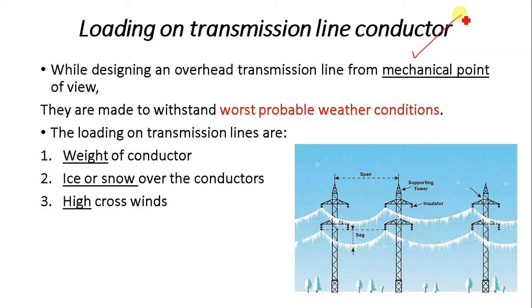The third loading type is high cross winds. In some areas you face stormy weather, so we have to consider the effect of wind because it causes additional load in the horizontal direction. In India, most areas have no problem of ice coating, so we can ignore the second point. But in areas like Jammu & Kashmir, Ladakh, Himachal Pradesh, Sikkim, and Arunachal Pradesh, where low temperatures are accompanied by snow and wind, the sag of the conductor tends to increase due to ice coating and wind pressure.